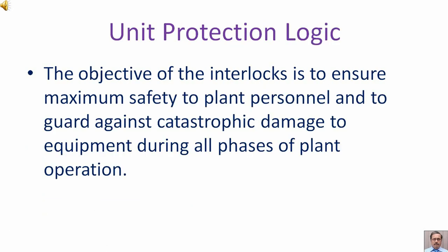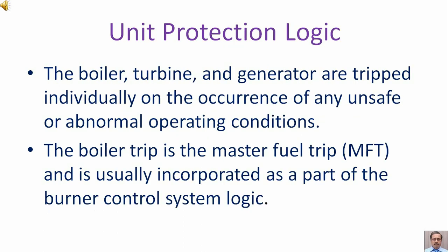The objective of the interlocks is to ensure maximum safety to plant personnel and to guard against catastrophic damage to the equipment during all phases of plant operation. The boiler, turbine, and generator are tripped individually on the occurrence of any unsafe or abnormal operating conditions. The boiler trip is the Master Fuel Trip (MFT) and is usually incorporated as a part of the burner control system logic.